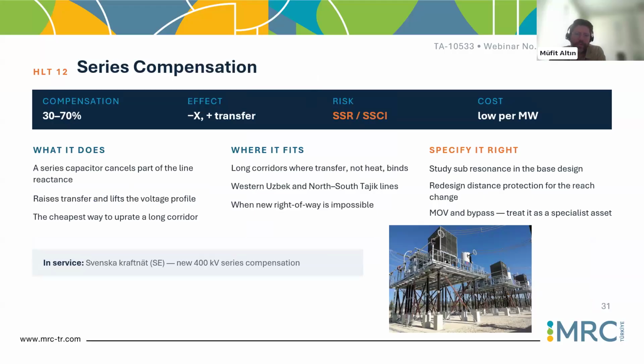Series compensation is a bit specific, of course. What we have talked about until now is more about controlling the bus with shunt elements. If you have long lines, then you need to install series compensation. This is more for static purposes. Of course, after the installation, you need to take care of SSR and SSCI issues, subsynchronous resonance and subsynchronous control interaction. But this is more in the planning stage. As far as I know from the Turkish system, we have south east to northwest corridors. We have series compensations. So yeah, probably in Sweden also they have north to south corridors. They installed the compensations. We can continue.